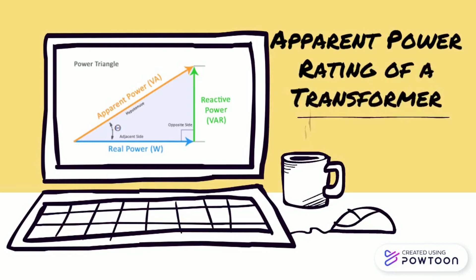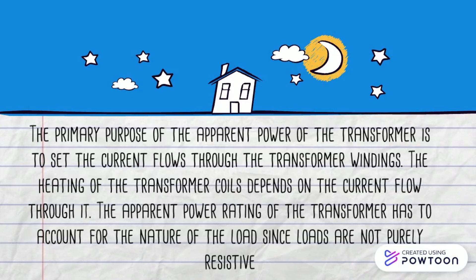Apparent power rating of a transformer. The primary purpose of the apparent power rating of the transformer is to set the current flow through the transformer windings. The heating of the transformer coils depends on the current flow through it. The apparent power rating of the transformer has to account for the nature of the load since loads are not purely resistive.